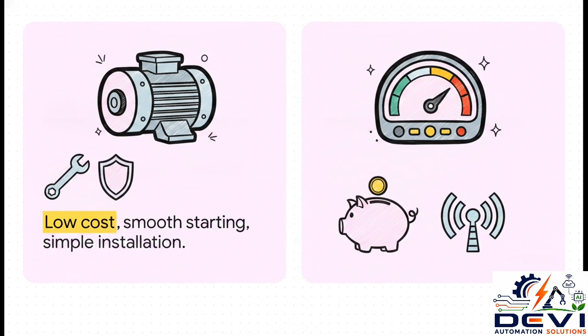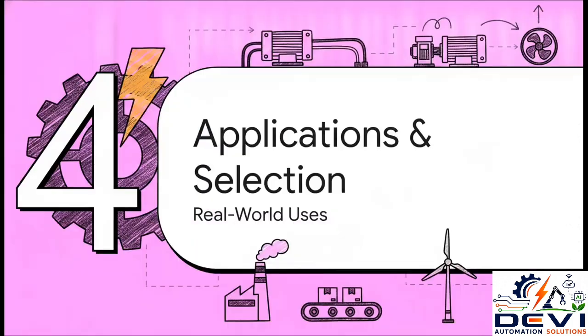On the flip side, the VFD's advantages are really geared toward the modern, efficient factory. It gives you total speed control, unlocks massive energy savings, especially on things like pumps and fans, and allows for deep process automation and remote monitoring. Section 4. Applications and Selection Guide.